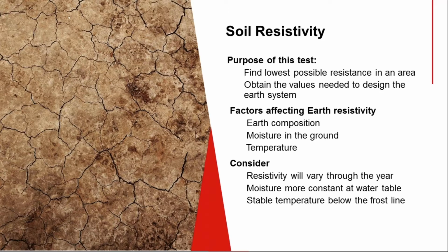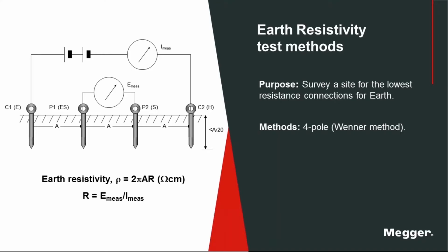If you install it too shallow, it has the same effect as a frozen car battery—ice doesn't conduct current, water does. So if you install a ground in relatively good weather and then a bad winter sets in while you're shallow buried, you could basically have no ground anymore until the spring thaw. Some places you don't need to worry about it, but if you're in that kind of environment, keep that in mind.